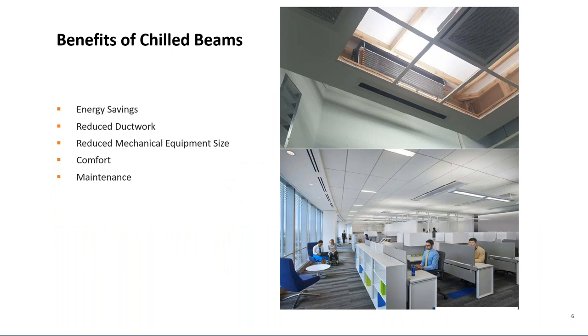And so why do we always consider chilled beams? Well, there's a number of benefits. One is that, in our calculations and also in the installations we've seen, where we've been able to record actual energy usage, there's energy savings compared to almost every other application. Now, everything I say here all depends on designing the system appropriately. As was brought up earlier when Nathan was presenting, you can certainly reduce the amount of ductwork on projects when you decouple the ventilation load that you need for the building from the sensible cooling load that you need for the building. And so there's a significantly reduced amount of ductwork and equipment size, even on the hydronic side, because of the energy efficiencies that you're gaining. And then again, when designed and when using the right chilled beam applications, there's a comfort and a maintenance benefit.